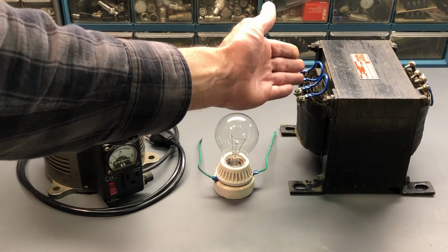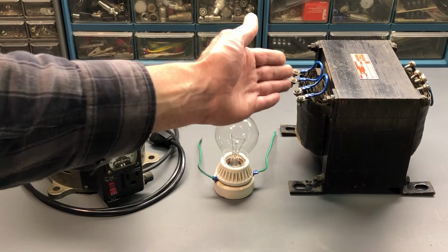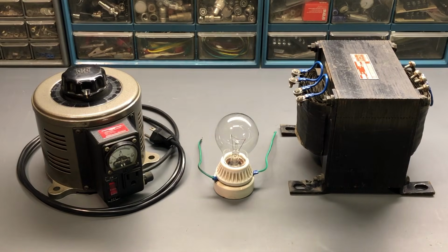This secondary has no reference to ground, so it greatly reduces the chance of electrical shock if you were to come in contact with a live or hot chassis that had that line connected, from the cord directly to the chassis. The isolation transformer is absolutely critical when testing that type of equipment. But again, it's a good idea when testing any type of equipment that you're working around the AC line, so that isolation is very useful.